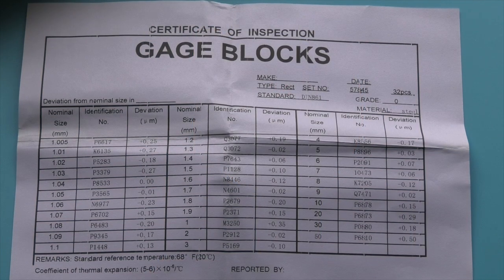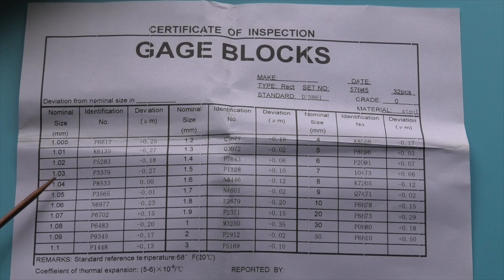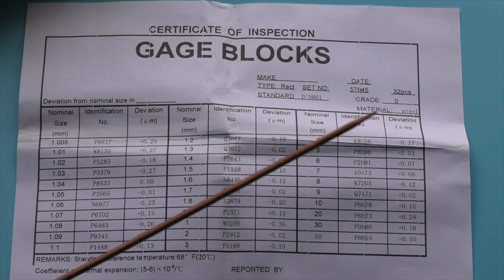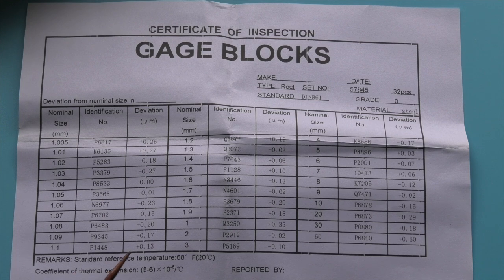This is the certificate of inspection or calibration certificate. You can see on the list, it lists each slip gauge. Each slip gauge has a part number on it, and it gives you the size of that slip gauge, whether it's plus or minus and how much out it is to the nominal in parts of a micron. And that goes through all the slip gauges that are in the set. It also states that we're tested at 20 degrees centigrade.